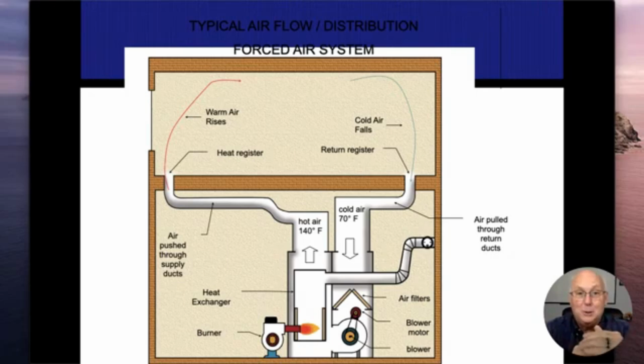Please don't take what I just said as me saying that it's okay to have a hole or a crack in the heat exchanger. It is not, by any means. All I'm saying is the design of these furnaces, we have multiple different safety features that are put into these things. So the first one is going to be our fuel air mixture. If that oil burner is doing what it's supposed to be doing, or my gas burners or propane burners are tuned right, I'm going to produce very low levels of carbon monoxide. The carbon monoxide is what's going to harm a human being. All right, so that's safety feature number one.